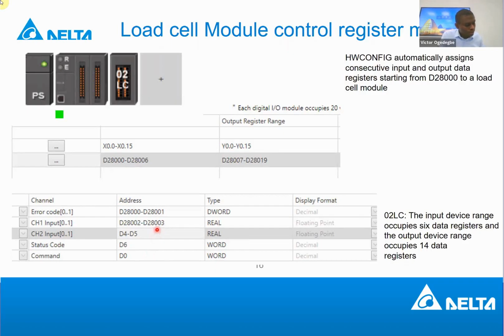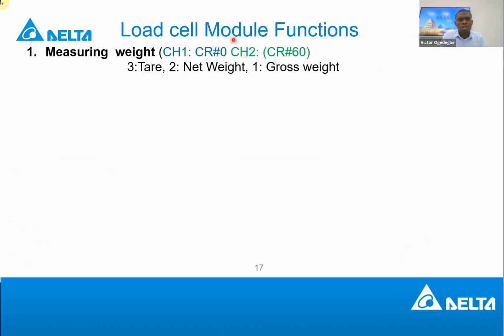So now let's wrap up this section with some of the functions of this load cell module. What can you achieve in your application if you decide to use this load cell module? One of them is measuring weight, the net weight. With this load cell module, the two-channel AS02LC, you can measure the weight and you can get those values in this control register.